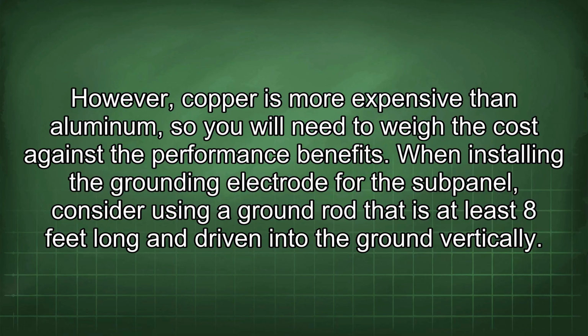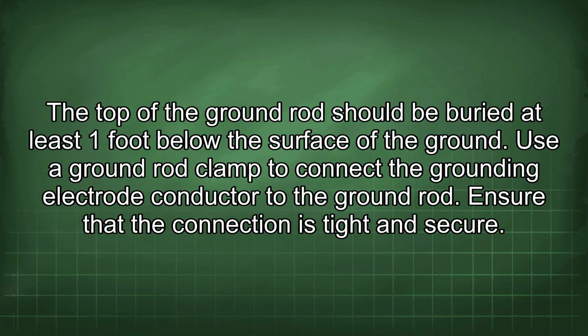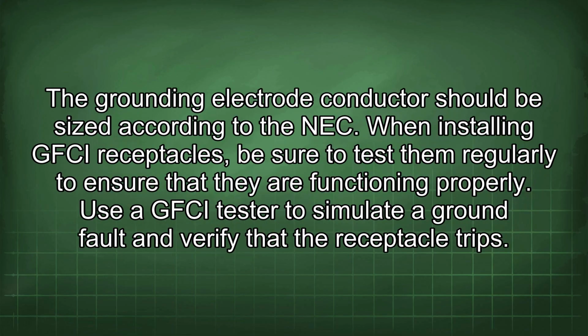When installing the grounding electrode for the subpanel, consider using a ground rod that is at least 8 feet long and driven into the ground vertically. The top of the ground rod should be buried at least 1 foot below the surface of the ground. Use a ground rod clamp to connect the grounding electrode conductor to the ground rod. Ensure that the connection is tight and secure. The grounding electrode conductor should be sized according to the NEC.